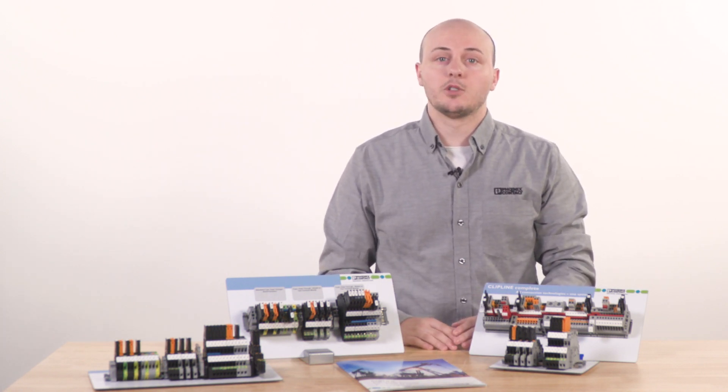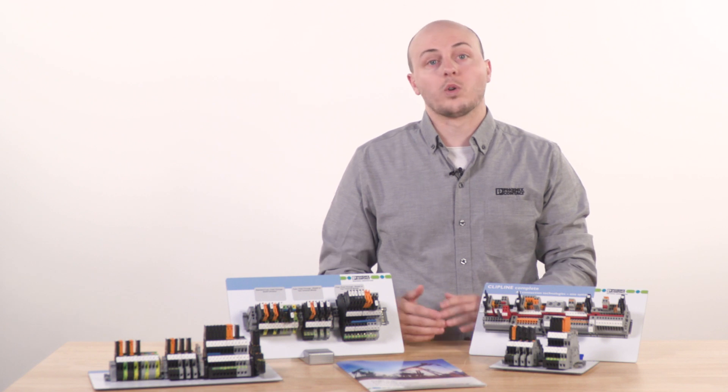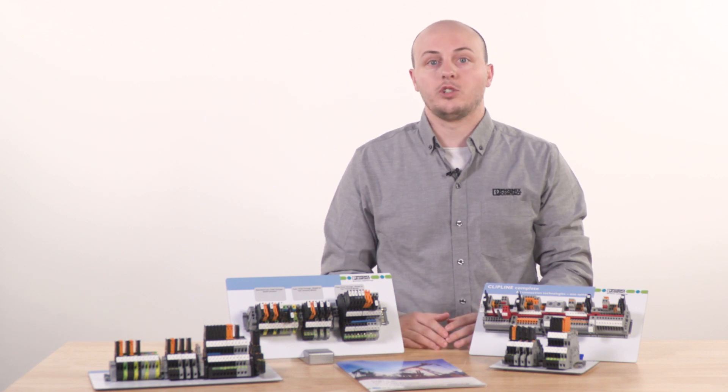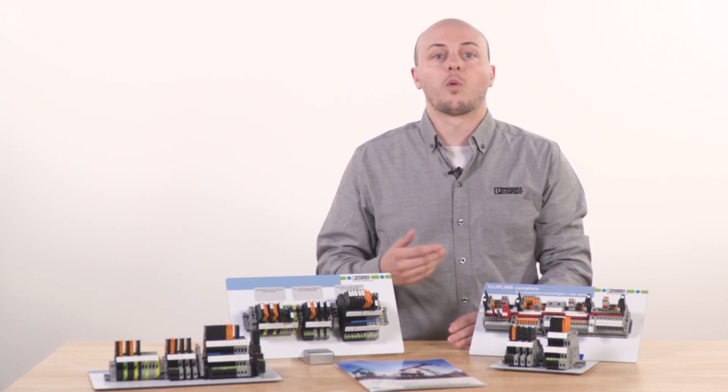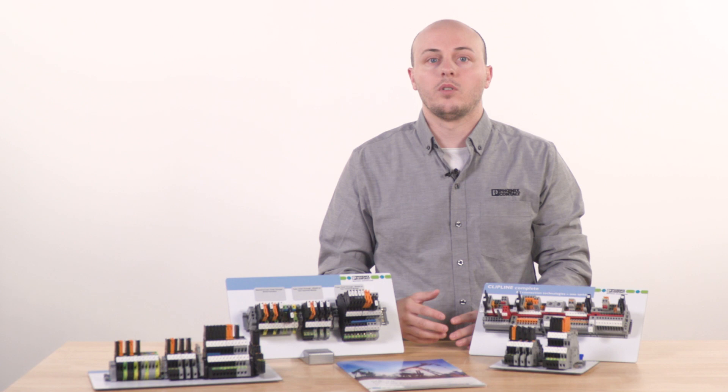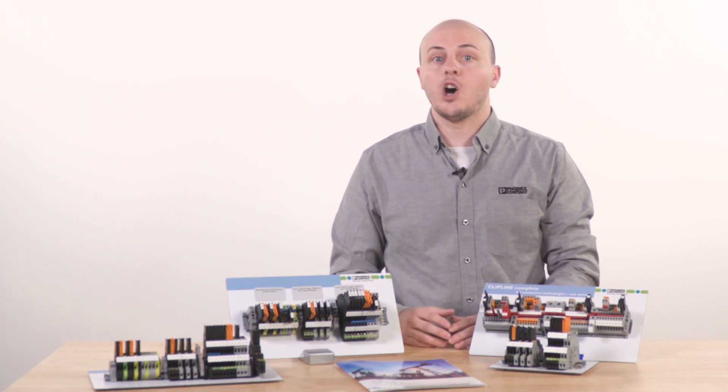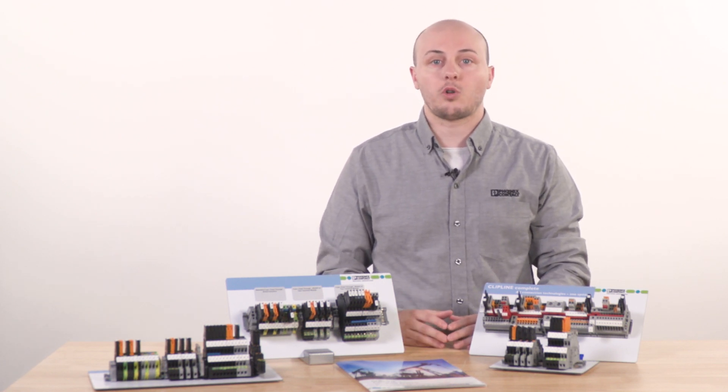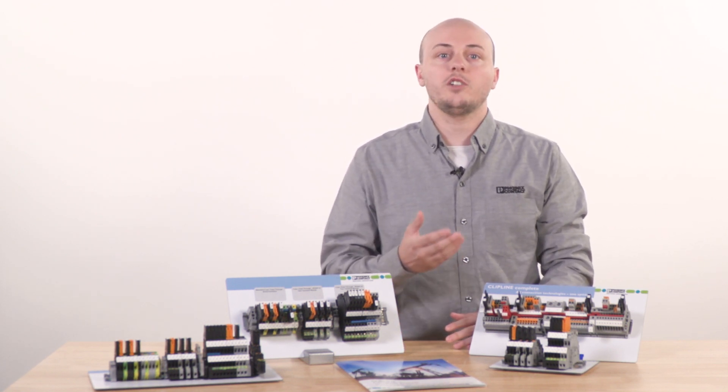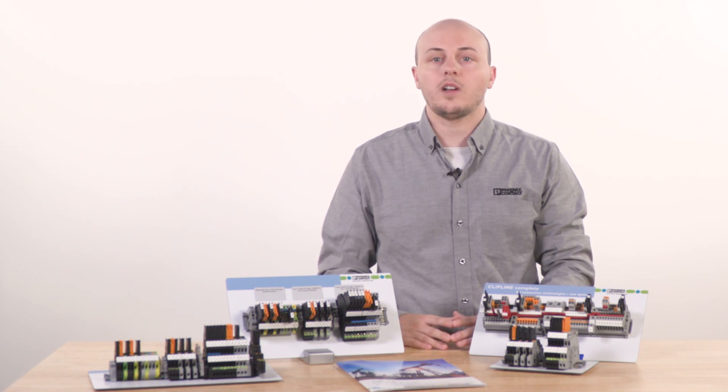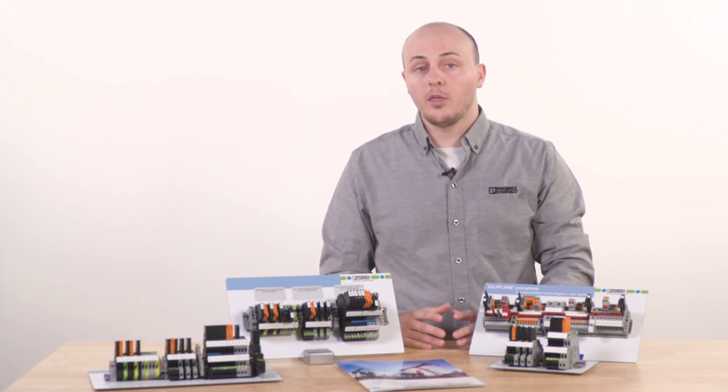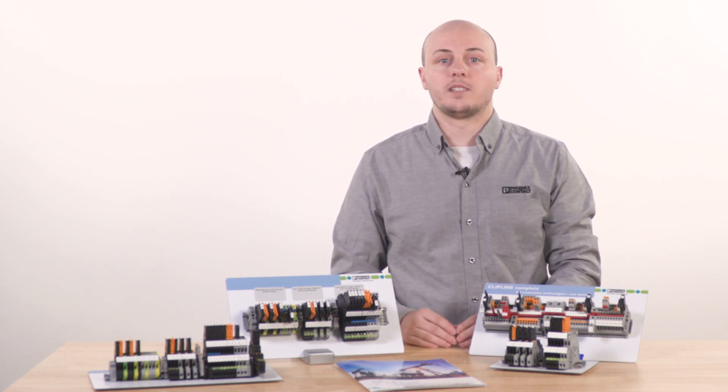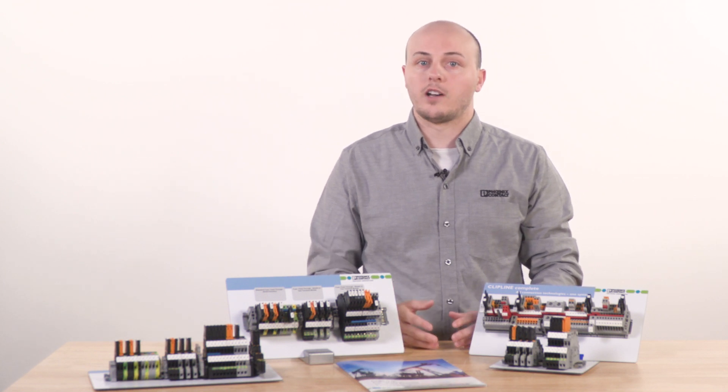Typically, these signals are transmitted in an analog or digital fashion using a shielded twisted pair or STP cable. To protect the sensors and I.O. of a process control loop, a fuse is installed in the circuit connecting the controller and field devices. Another termination point is necessary to carry the shield to ground.